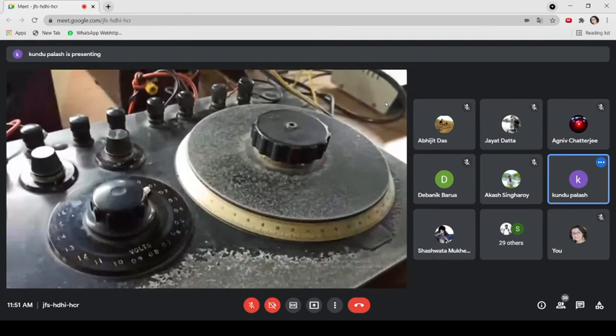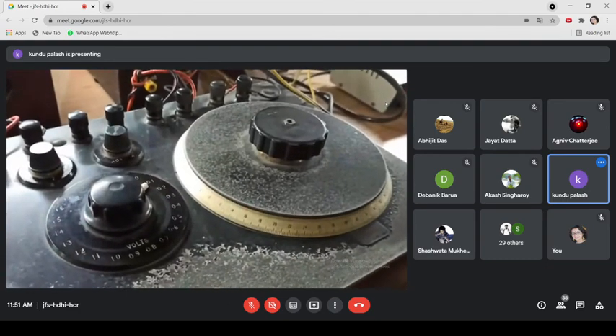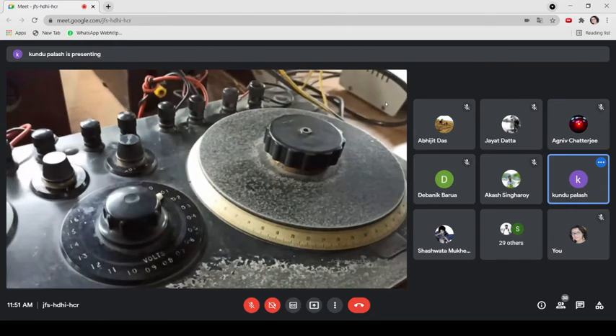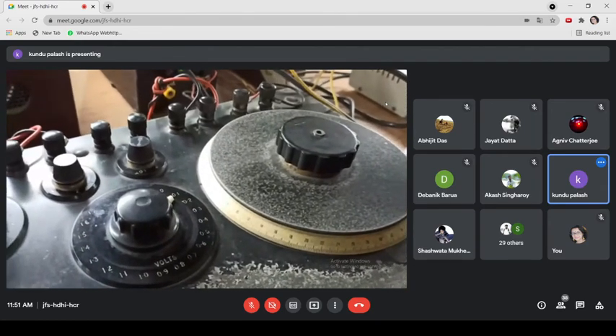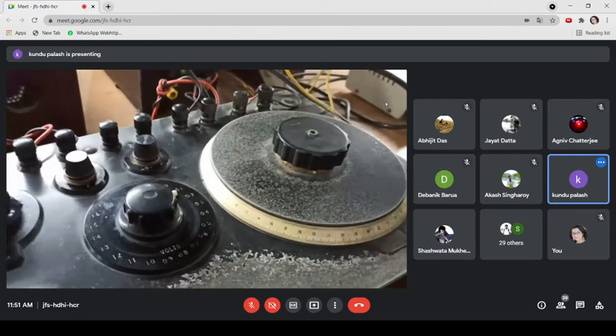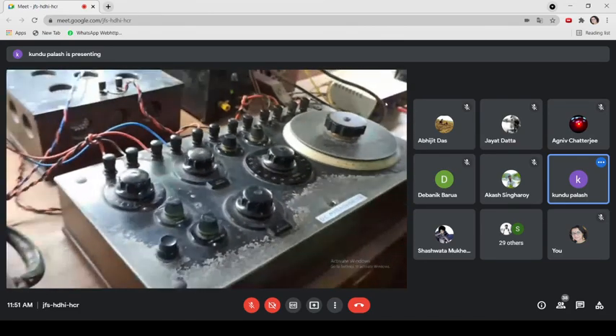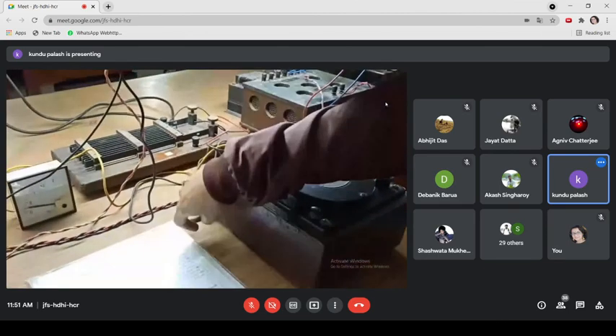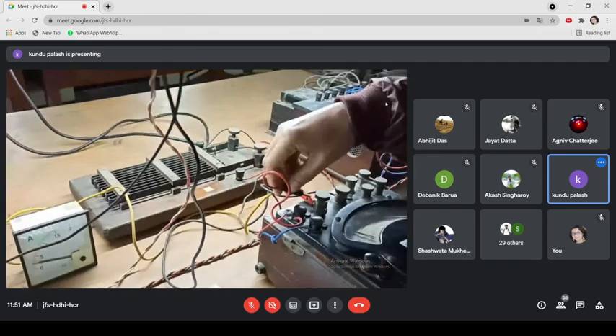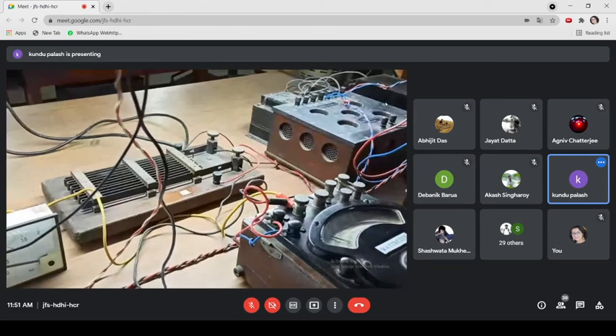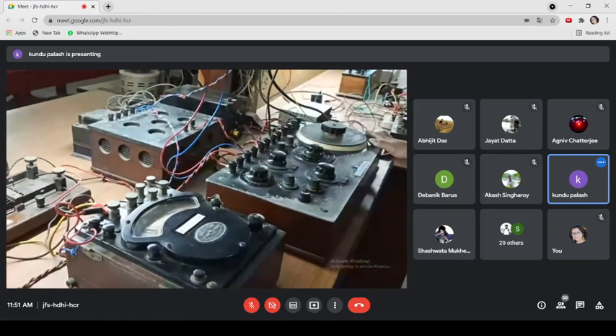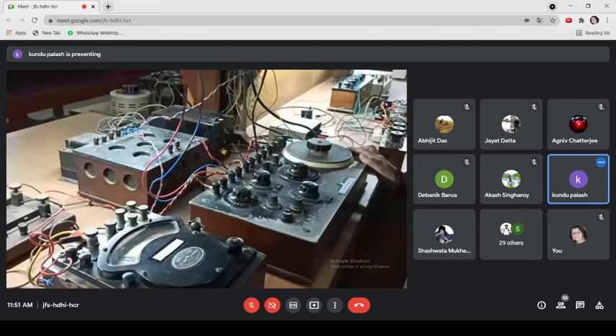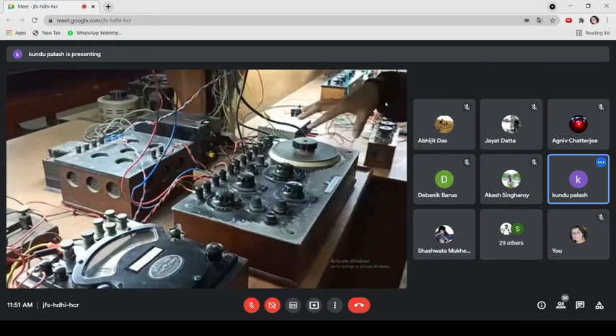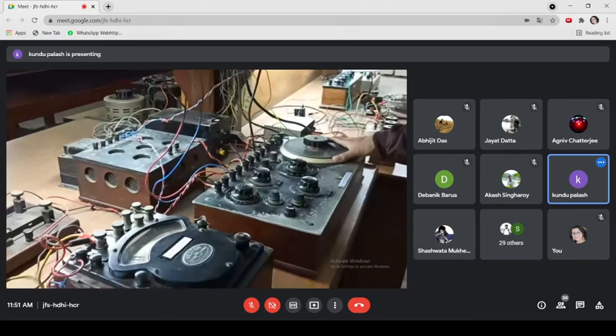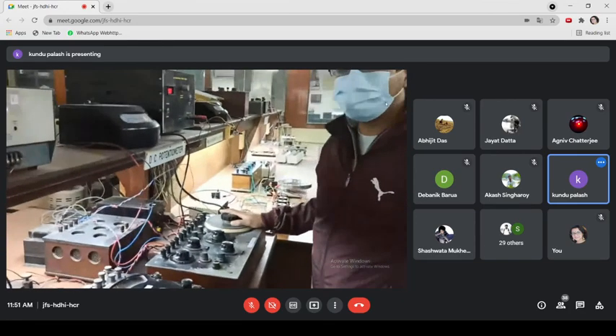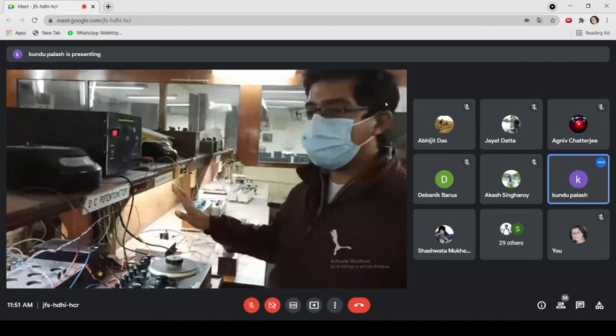In the same way, we will take the reading of the current coil calibration, and further we will connect the link, connect the potential coil with the current coil, and do the same process. Check whether the circuit is balanced or not. We will do the same thing again. We will switch the level and get the null point.